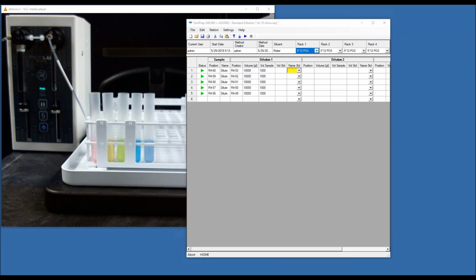And then those were run on the ICP. We paired that blank with the initial blank at the beginning of the calibration curve for a comparison, and that's where the carryover data came from. And we did use some fairly significant mixing and rinsing parameters on that, but again, it's totally up to the user. So depending on the needs of your lab, you can add or remove rinse time to optimize performance for your own system and what your own needs are.